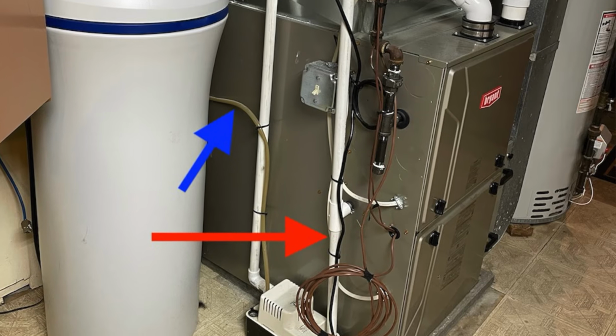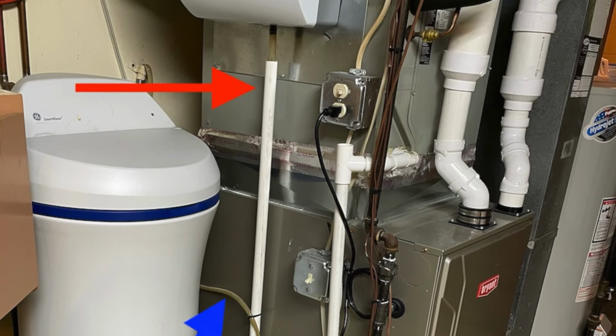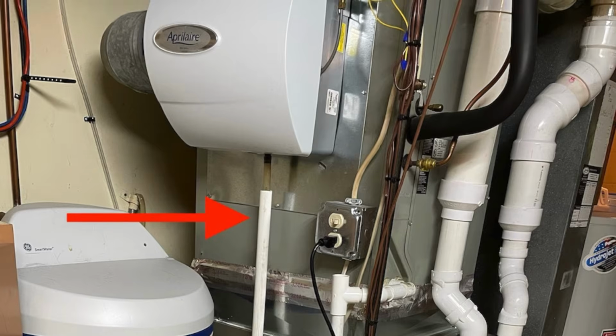Before I wrap up, just some other things to note. We noted the drains and the flue vents, making sure that those things are maintained but also installed correctly, making sure that the drain continues to have fall. I've seen simple things such as a strap coming loose and now we've got a droop in the flue pipe or the drain. And of course, the big one, making sure that air filters are replaced or cleaned periodically.